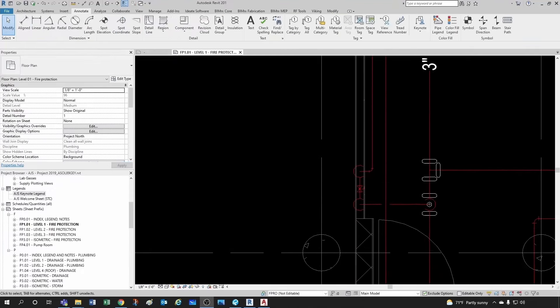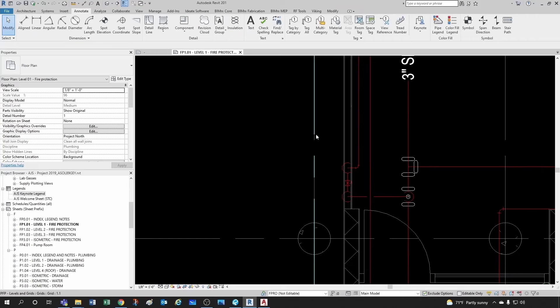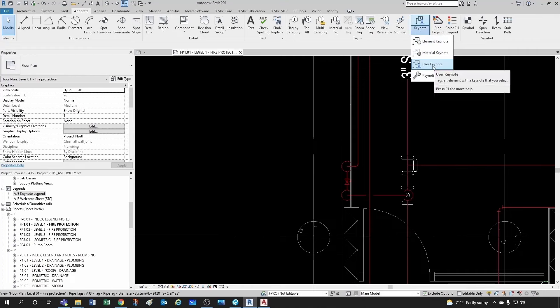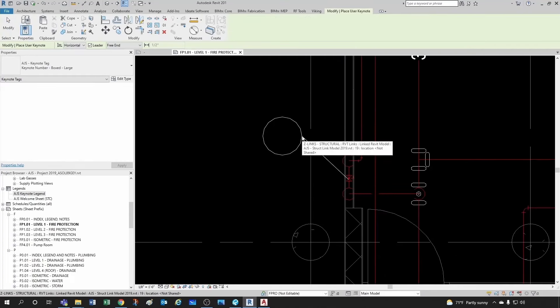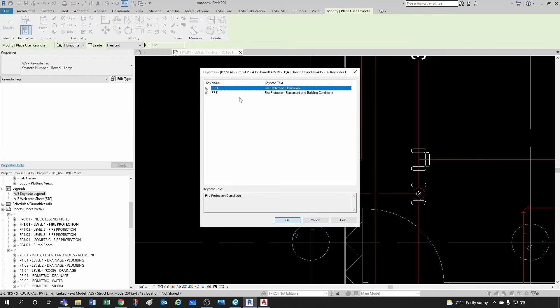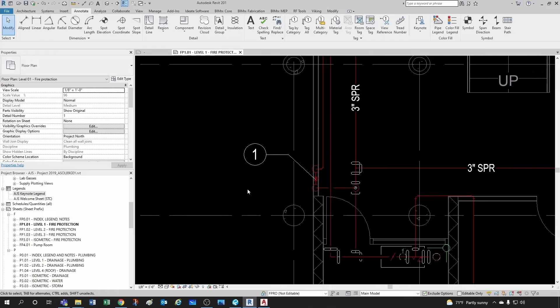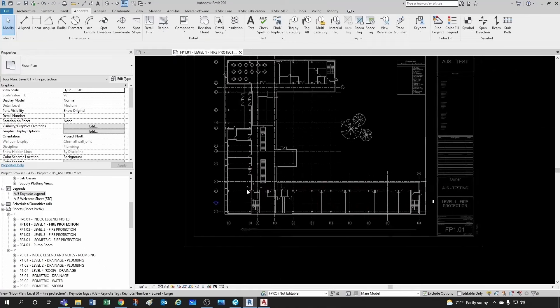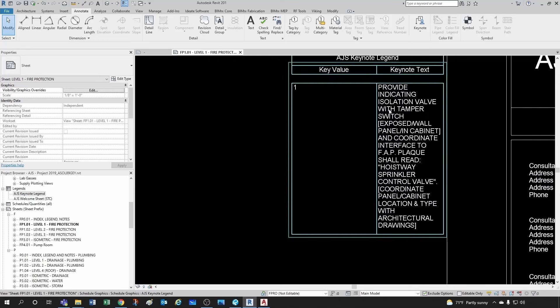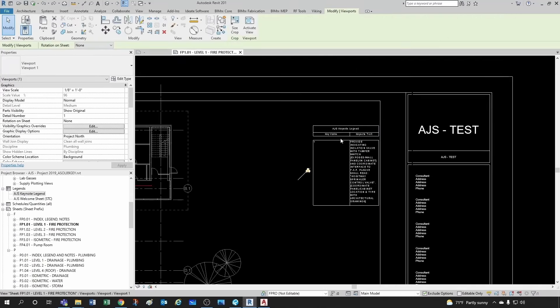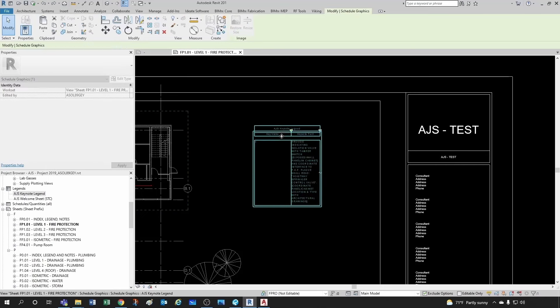Another way of using keynotes — a different type — is the user keynotes. Let's do the same valve we were doing before. Now it's prompting me with this simple file I created for explanation purposes. In this case this is for fire protection. We have our note here FP5, which is an indicating isolation valve with tamper switch. I just placed it here, and now if you go out into your sheet, this is my note right here.